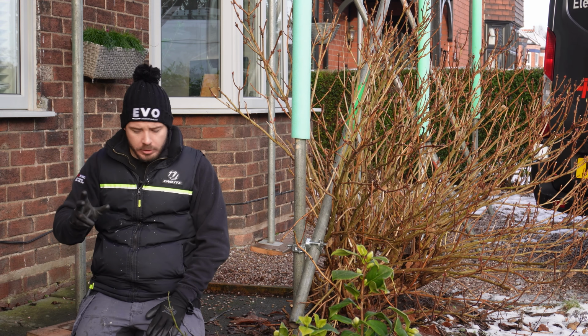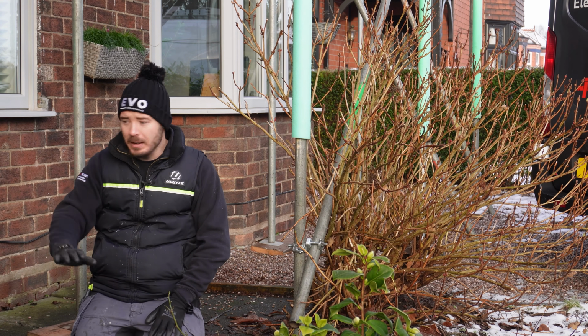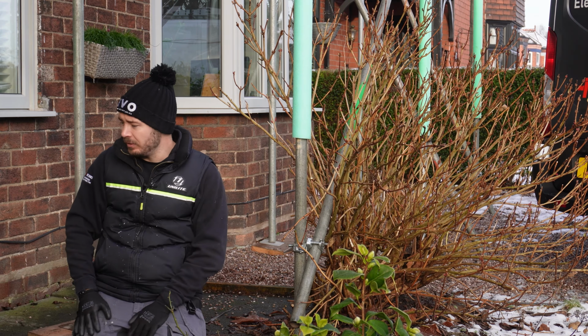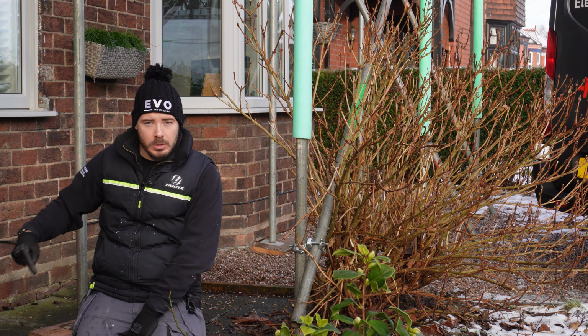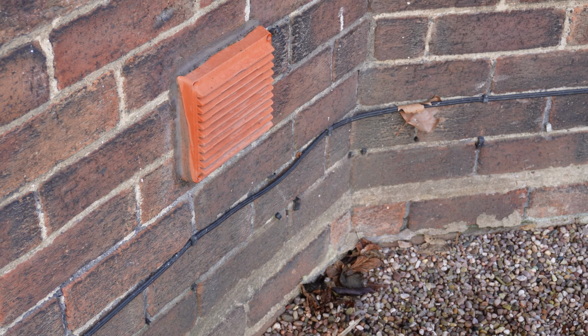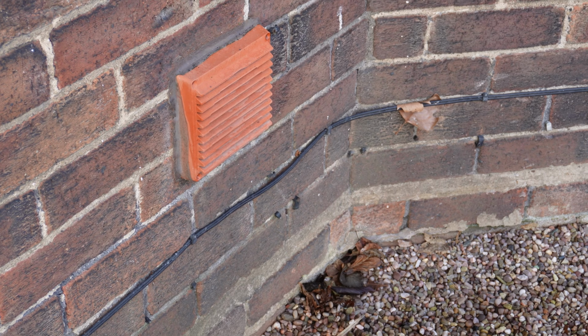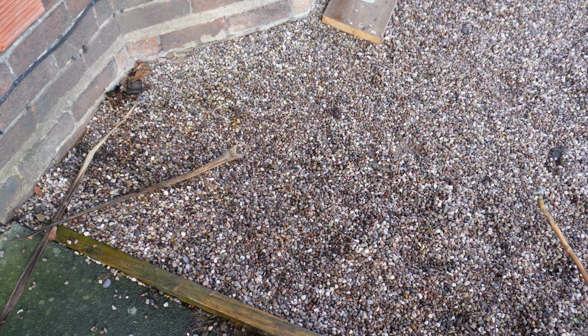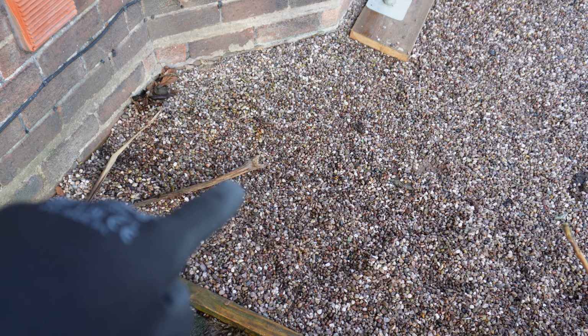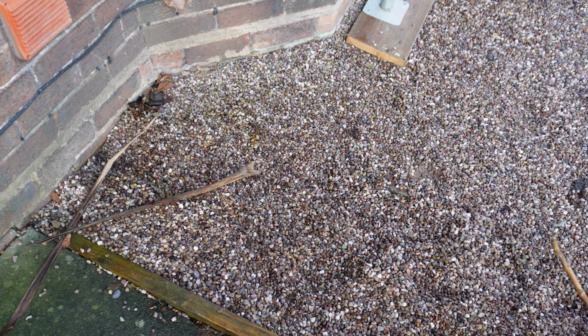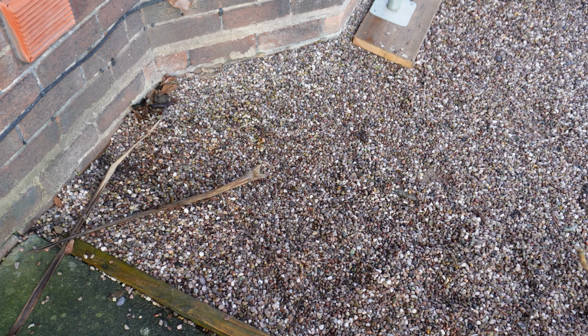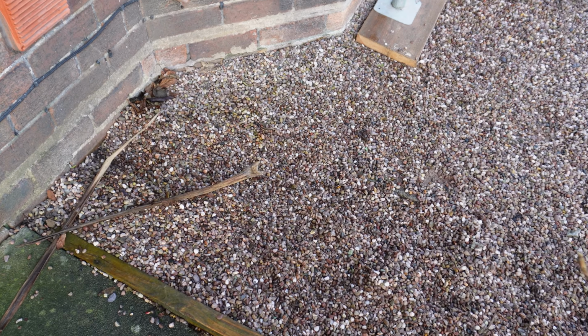But when we're looking at putting the earth rod in, we want to stay away from the flags. We don't want to be lifting flags, and we certainly don't want to be drilling through, because we're not going to get a good reading. We want to stay away from all of this concrete. But if we can get a rod out on the wall here, we've got options to use a bit of conduit and get into an earth box. We can bring it a bit further out here so we've got space to stay away from the footings of the building, and there's no surfaces coming in this way. Somewhere around here works a lot better.